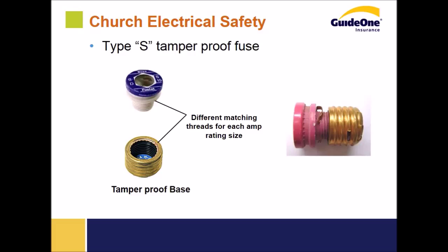However, we do require that they have Fustat holders and use Fustats, which simply help prevent overcurrent. Most commonly, we would see a kitchen circuit that should have a maximum of a 20 amp fuse with a 30 amp fuse screwed in. Or we'll have a lighting circuit that should have a maximum of a 15 amp fuse, with a 30 amp fuse screwed in place. Those types of conditions need to be safeguarded against by using Fustat holders and the appropriately sized fuse, as prescribed by a licensed electrician.